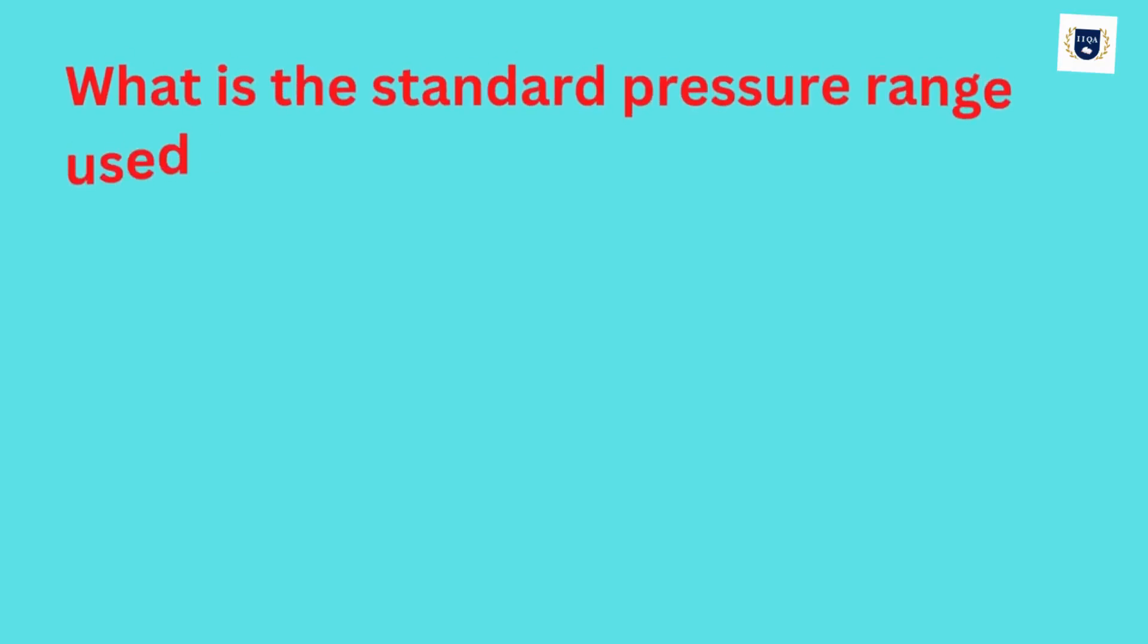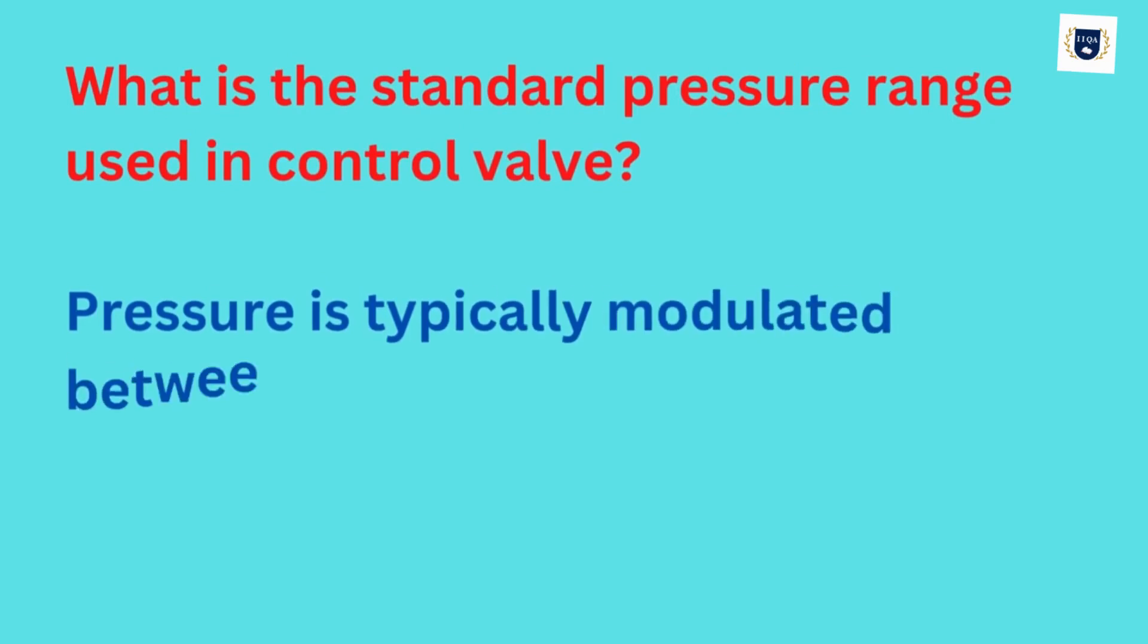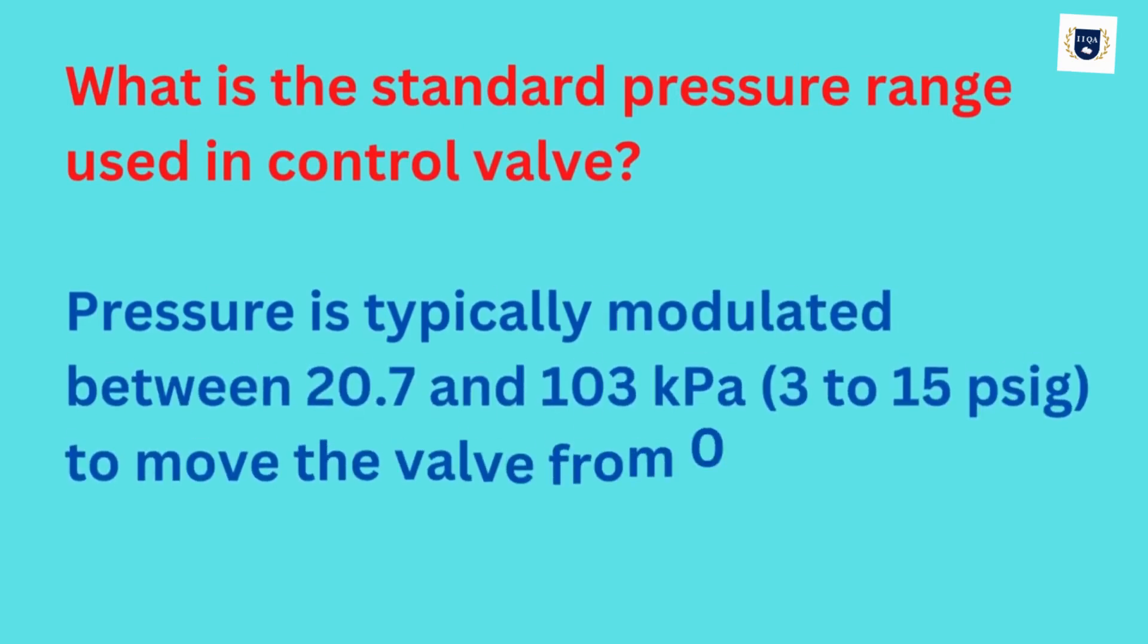What is the standard pressure range used in control valves? Pressure is typically modulated between 20.7 to 103 kPa, or 3 to 15 psi, to move the valve from 0 to 100% position.